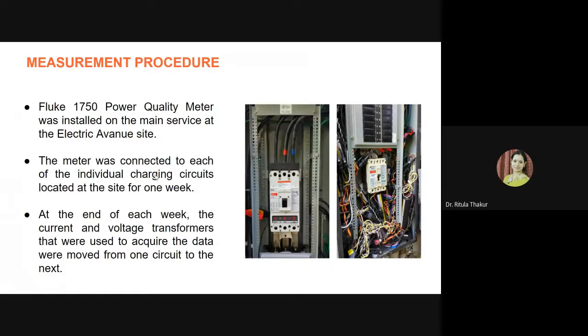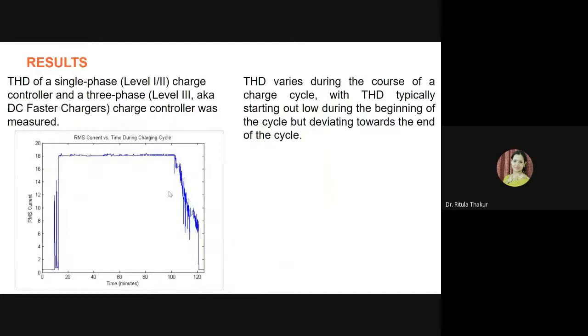And what they did is that they connected to each of the individual charging circuits at the site for 1 week, and at the end of each week, the CTs and PTs used to acquire the data were moved to the next circuit. But as I will tell you in the coming slides, compared to a single charging station, the cumulative effect of all the charging stations leads to a more prominent effect, or generation of harmonics. And this is one of the results of the THDs.